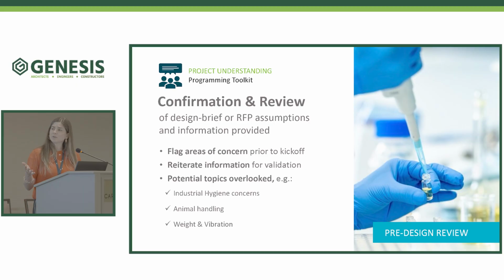As a specific example in this topic, on a small project recently that involved a small lab component to a larger renovation project, the facility management team had documented as part of the design brief that the small lab that was supporting MRI prep work did not have BSL-2 ventilation or design requirements.